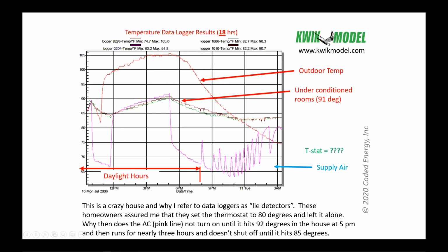So the green line is the temperature at the thermostat. And they told me they were going to keep it at 75, 76, whatever it was. But the pink line is the supply air temperature. If you look, the air conditioner turned on when the temperature at the thermostat was almost 90 degrees, like 89 degrees. So when the green line was 89 degrees, the air conditioner comes on. So they let the house get up to 89 degrees and then they drop the thermostat. I don't know what they dropped it to until I follow this pink line and see when it turned off. So it turns off right here, and when it turned off, the thermostat was at 84 degrees. So they had dropped their thermostat from whatever it was down to 84 degrees, and that's when it turned off. So I can tell what their thermostat set points are.